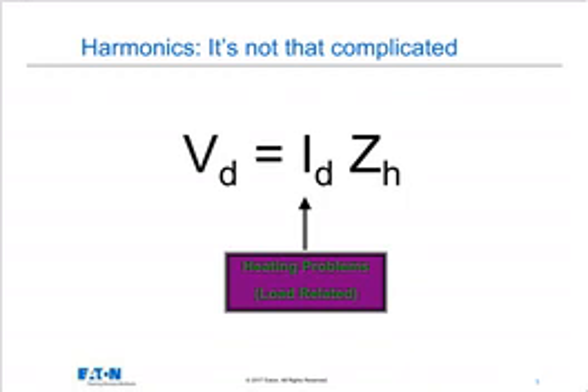So I start out with a system that's fairly clean, 60 hertz, and I inject current distortion. Without that current distortion, my voltage distortion is 0. But the more current distortion I add, the more voltage distortion I get.